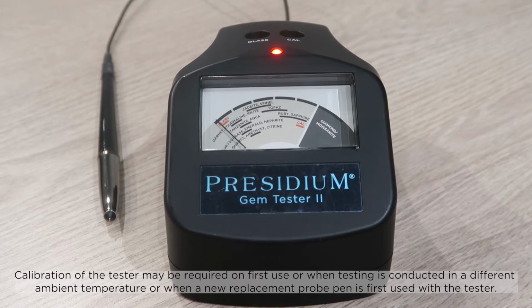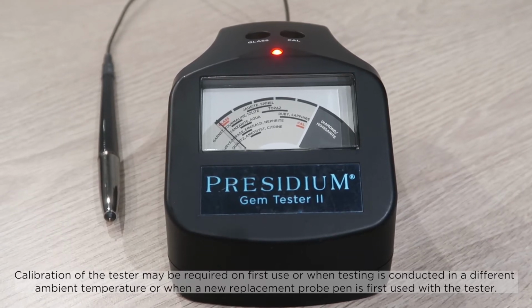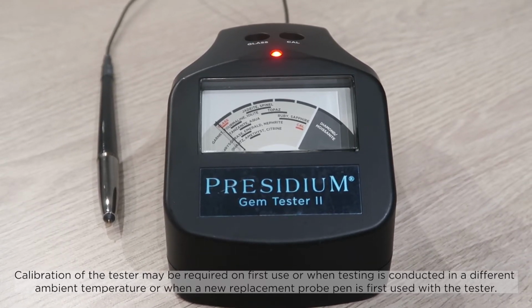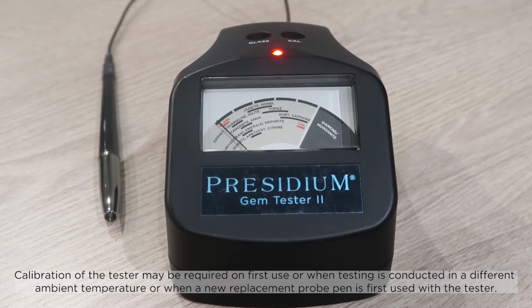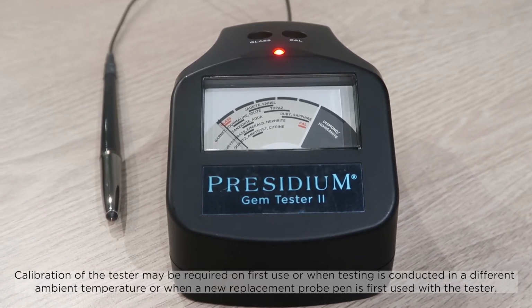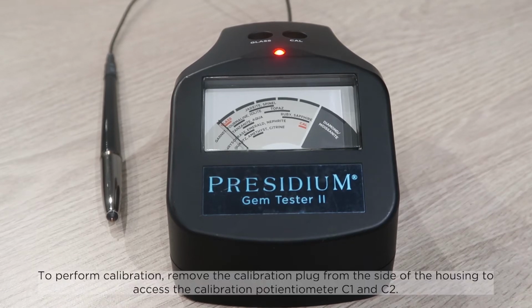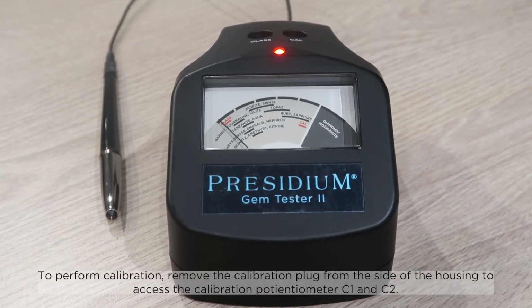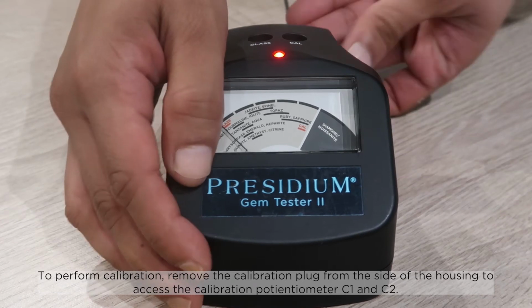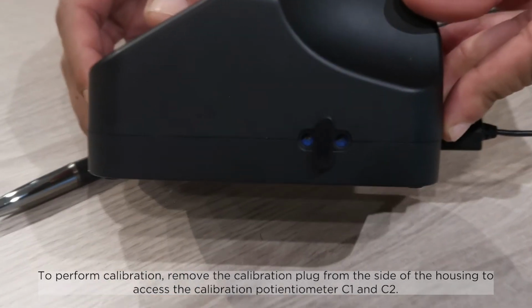Calibration of the tester may be required on first use, when testing is conducted in a different ambient temperature, or when a new replacement probe pen is first used with the tester. To perform calibration, remove the calibration plug from the side of the housing to access the calibration potentiometers C1 and C2.